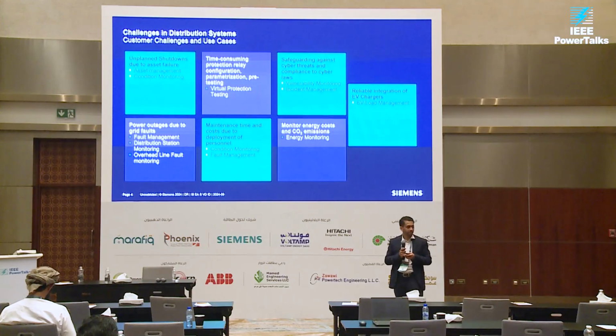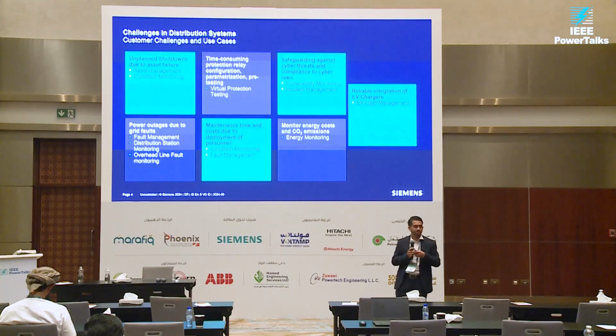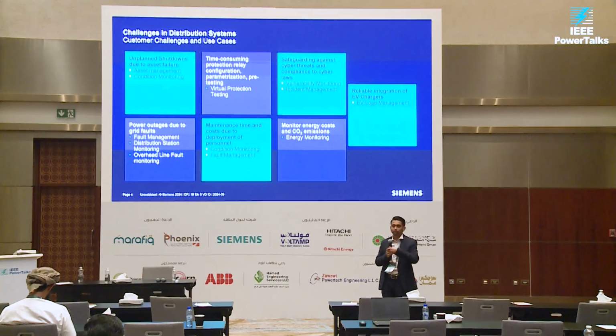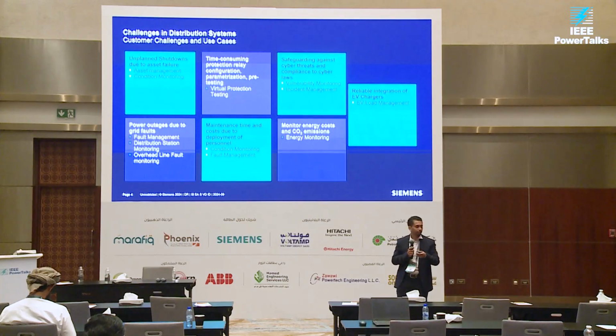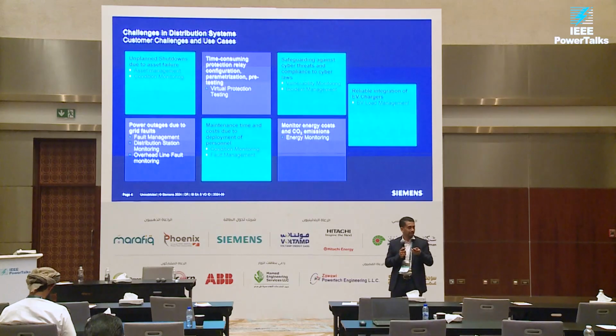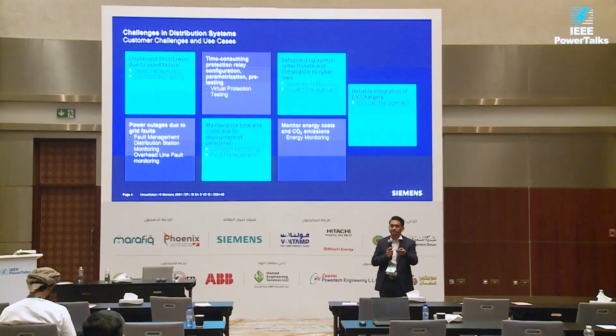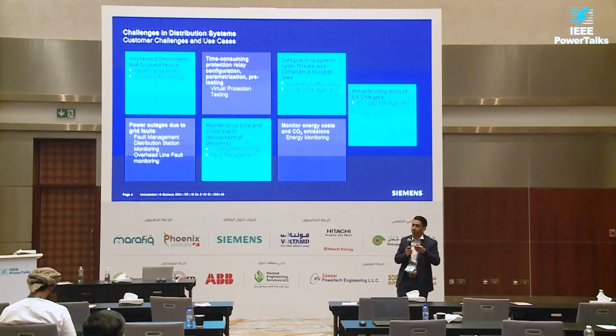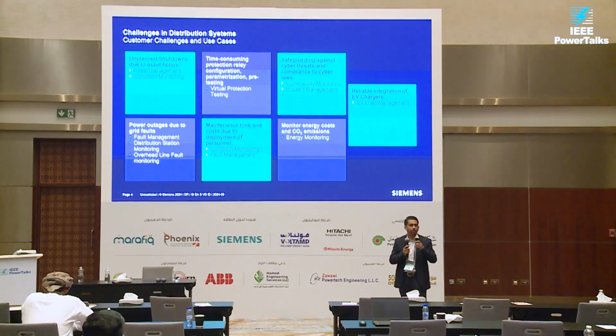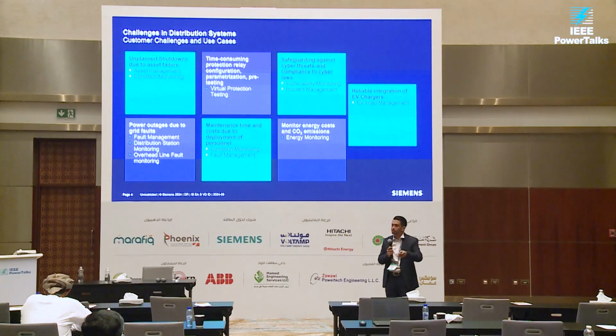Coming to the substation side, primary station, you have protection relays. You do changes on the protection relays, so you need a physical device to test the protection relays. For example, if there is a fault in the station, you want to simulate that fault in a lab environment to see what exactly happened. So you need software which can help you, so that instead of having a physical relay with you, you can simulate the fault on a virtual relay which will replicate the actual physical relay. In that way, you can faster analyze the fault without having to connect your relay with an Omicron kit, current injection kit, and then do the simulation.